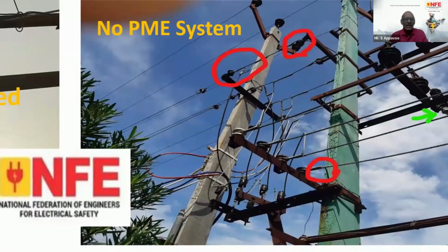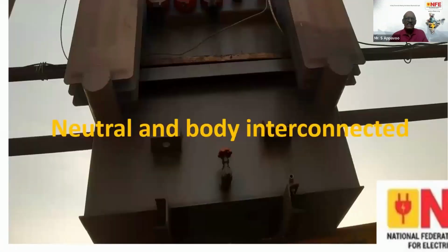But naturally, space constraints dictate to the supplier. The supplier is not in a position to segregate his earth electrodes to provide insulation. So we can assume that the frame as well as the neutral are connected, whether directly or inefficiently through the close positioning of earth electrodes. These are the things the supplier has to take into account. In all the cases, whether it is a distribution transformer, a substation of the DISCOM, or the consumer substation, there is an unavoidable proximity of body and neutral earth electrodes. Due to this, the influence of earth electrodes will also be there. So it is not practical to separate them. Also, any separation in such cases will be almost an inefficiently connected one. So here it becomes necessary to connect the system.